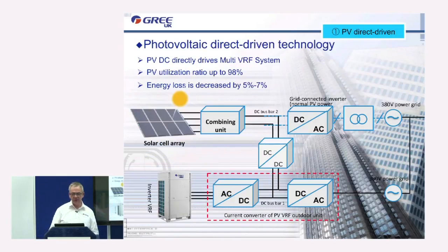So with these main elements it's easy to see the advantages of this system. First of all, the direct driven technology. As I've already mentioned, we utilise the ratio of PV up to 98%, and because we only have one item on the bus bar, our losses are massively decreased. So energy losses are decreased by up to 7%. Every time there is a component in the line, losses will be experienced. So if you reduce the number of components in the line, then your losses are decreased. What we saw there was a normal system where we have to have grid connected inverters, we have to have conversion from DC to AC. Well, we can get rid of those components because we do it all within the unit and the flow is controlled within the unit.